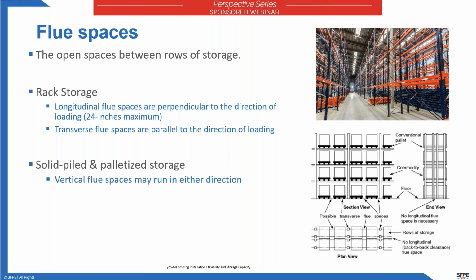In order to have effective fire protection, particularly with ceiling-only fire protection, it's important that the sprinklers operate as quickly as possible after the fire event has occurred. The flue spaces, as the name implies, allow heat to rapidly rise vertically to get to the ceiling. That heat gets to the sprinklers, and then the sprinklers are able to operate. The second phase is that we want the water discharged from the sprinkler to cascade down and penetrate the rack to address the fire. Those open flue spaces provide the passageway for water to travel down to the fire. So appropriate flue spaces are important when using ceiling-only fire protection.